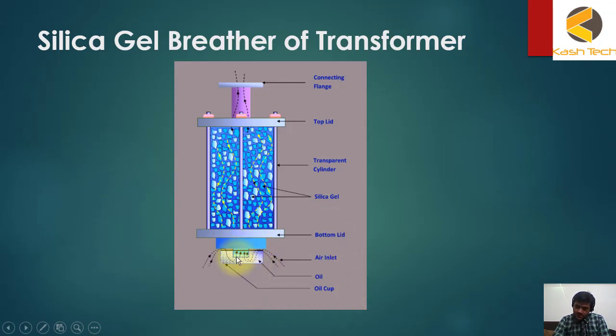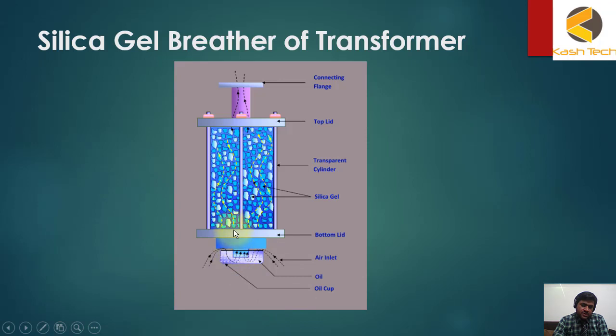You can see here there is a transparent cap, and inside it you will find oil. When air enters at the side of the breather, it passes through the oil which cleans the air from dust and other particles. From there the air goes upward and passes through the silica gel to the top of the transformer, also absorbing moisture along the way.